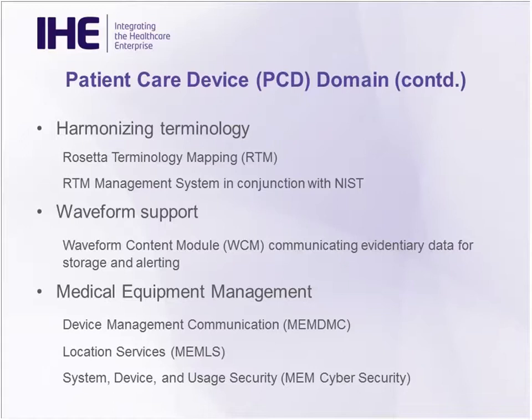We have a couple of areas that we focus on in medical equipment management. One is the communication of observations by the devices to things like the computerized maintenance management systems, the location of things, be those things devices or people in the healthcare realm, and then the secure use of the devices. So we focus specifically on cybersecurity, involving things like the protection of the device from hacking and also updating of the devices for things like patch management.